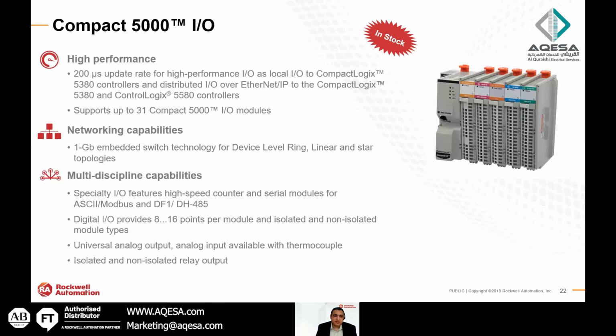The new CompactLogix 5000 has a 200 microsecond update rate, and for the fast one, a 10 microsecond update rate, high performance. It's compatible with the 5380 and 5580 controllers. As I told you, the new IOs can be controlled by the new controllers, but not the old controllers.